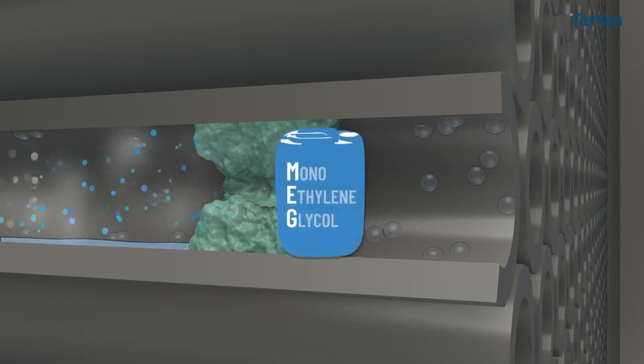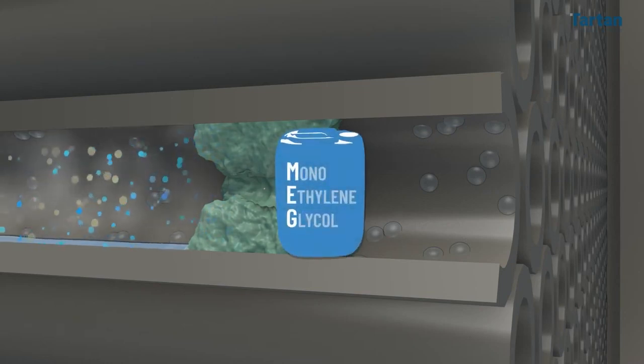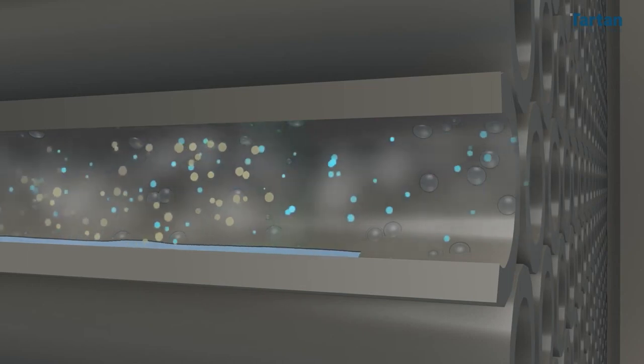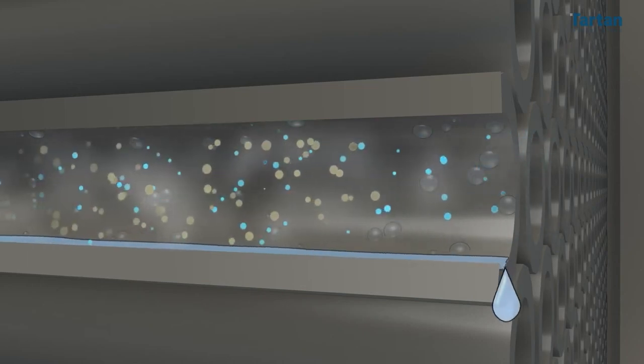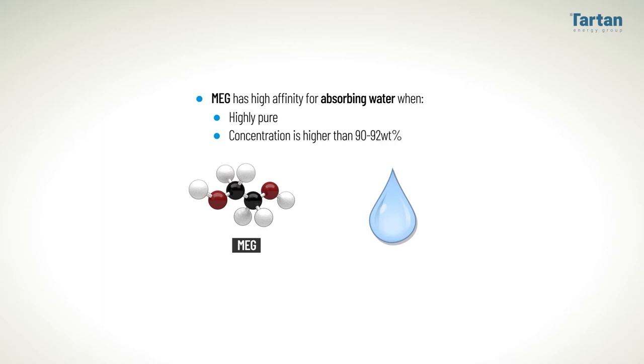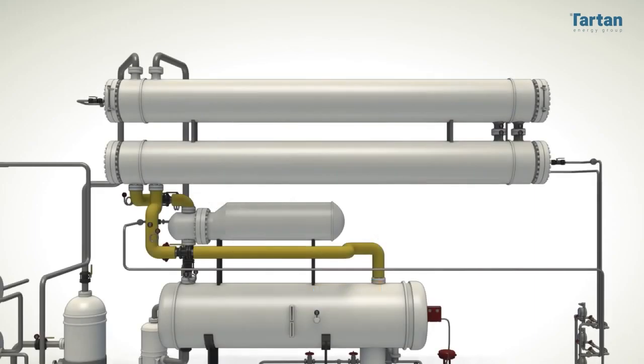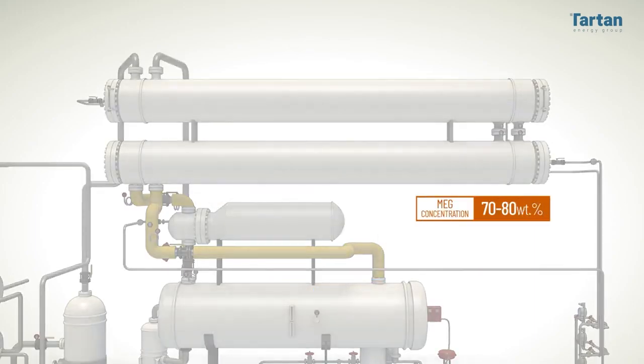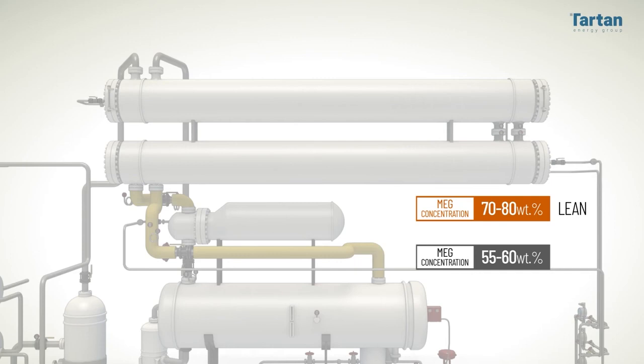That is why MEG, a chemical inhibitor, is injected into the exchanger and functions as an antifreeze. Although MEG has high affinity for absorbing water, it only does so when highly pure and its concentration is higher than 90-92 weight percent. While in a regeneration unit, MEG's concentration is typically between 70-80 weight percent in the lean solution and between 55-60 weight percent in the rich, so the water is not absorbed.